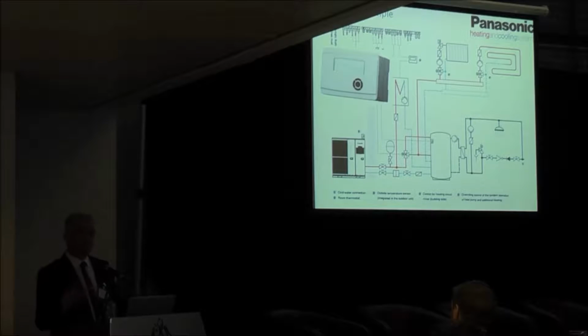You would obviously put in an 800 litre buffer, a 1000 litre buffer or whatever, if you were going to utilise a system like this, and you'd have some means of isolating that when your PV wasn't available. But you can do anything. You can engineer anything into a project. The space is always going to be a consideration. Cost is always going to be a consideration. But the technology is there now for the heat pump to look at the solar, to look at the PV, and to integrate with it.